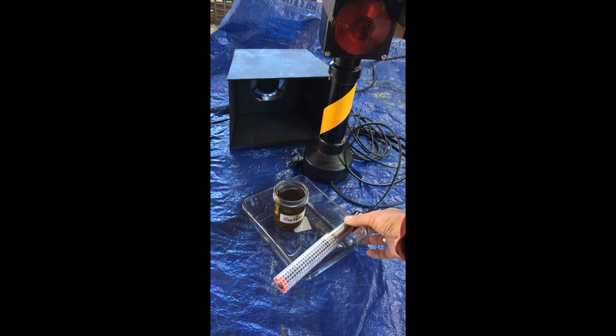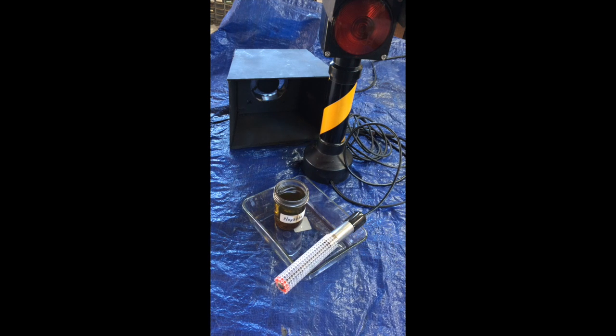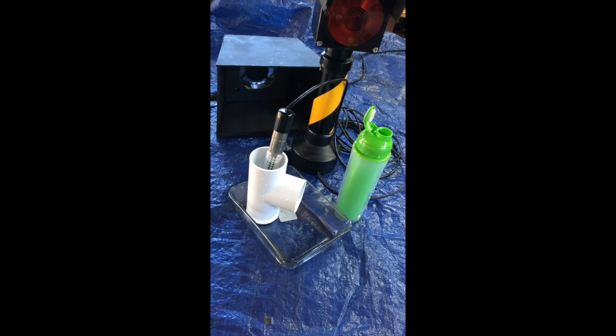I'm going to set it here on the drip pan, and if I try to reset at this point, nothing happens because the probe is still in the alarm state. It literally will take 15 or 20 minutes for the naphtha to evaporate and let us reset the probe. So we're going to stop again here and come back for phase 3, which will be the tap water rejection test.